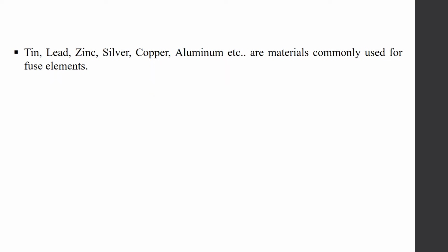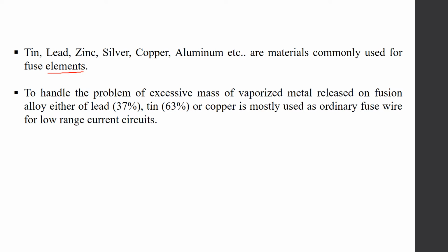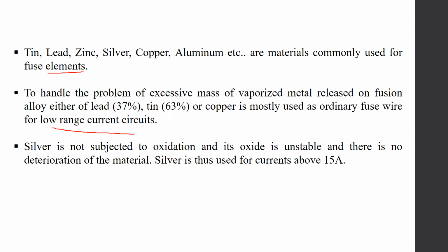Generally, tin, lead, zinc, silver, copper, aluminium, etc. materials are used for making the fuse elements. During the abnormal condition, when the current exceeds the predetermined value, the fuse wire melts down and the vaporized metal released here can cause a problem, and therefore an alloy of either lead, tin or copper is generally used for making the ordinary fuse wire for low range circuits. Also, we can use silver, as silver is not subjected to oxidization, but as we know, silver is a costly material and thus it is used for currents above 15 ampere only.